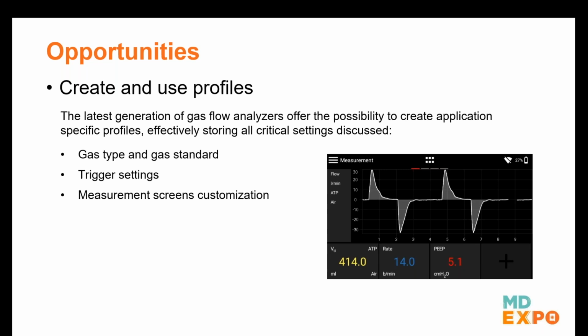And most modern gas flow analyzers offer this feature: you can save all that as a profile, name it somehow, and then load it later on. This helps minimize the risk of setup-based, settings-based errors and reading errors. Some gas flow analyzers even allow you to group the measurements and color them differently, which is really nice sometimes. For example, if you have all your pressures in red, then it makes it easier for you to allocate the value you want to look at more reliably.